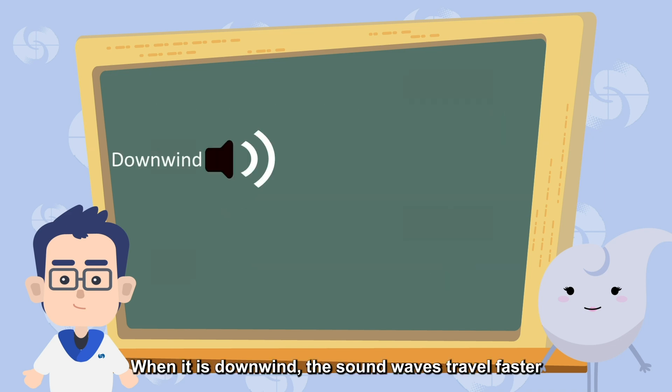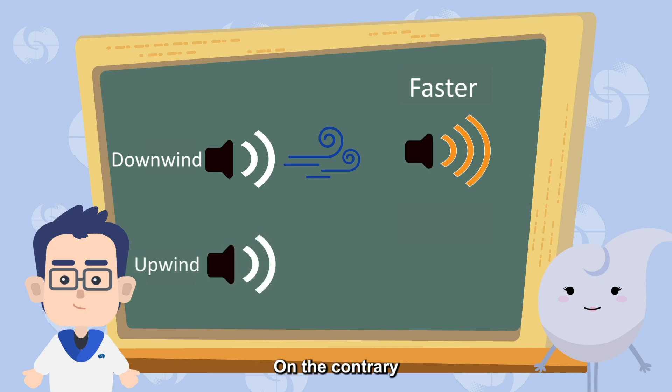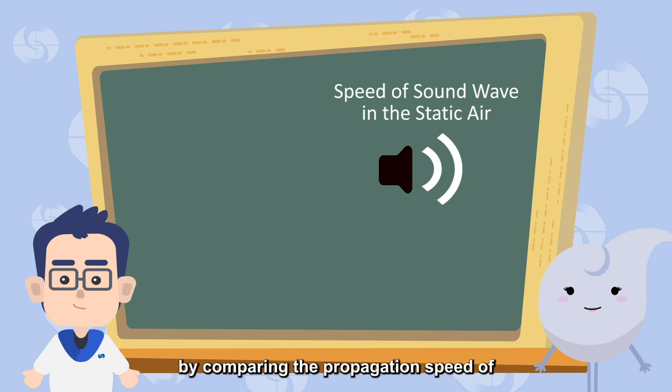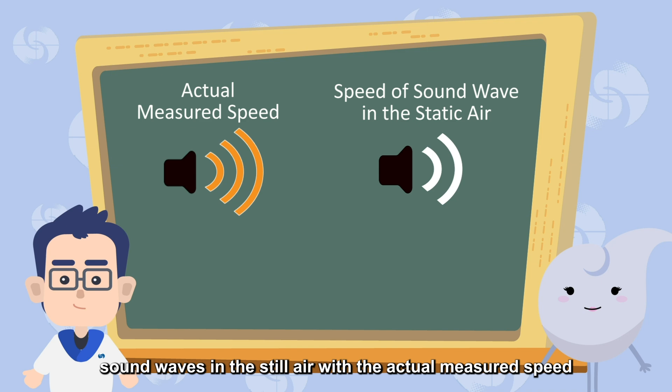When it is downwind, the sound waves travel faster. On the contrary, the sound waves travel slower when it's upwind. Therefore, the wind speed can be calculated by comparing the propagation speed of sound waves in the still air with the actual measured speed.